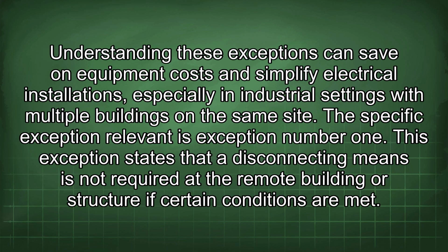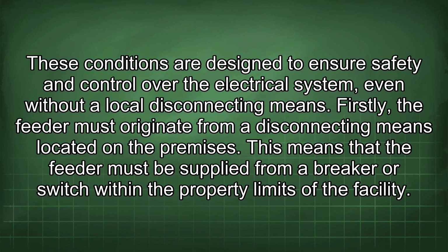Understanding these exceptions can save on equipment costs and simplify electrical installations, especially in industrial settings with multiple buildings on the same site. The specific exception relevant is exception number 1. This exception states that a disconnecting means is not required at the remote building or structure if certain conditions are met. These conditions are designed to ensure safety and control over the electrical system even without a local disconnecting means.